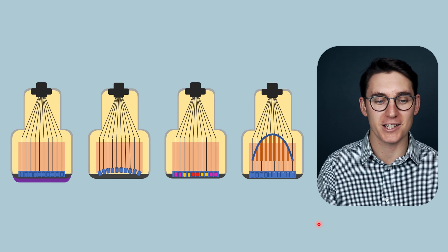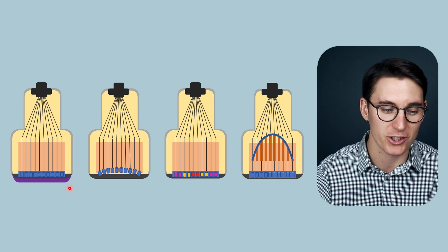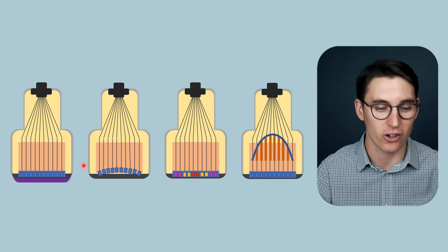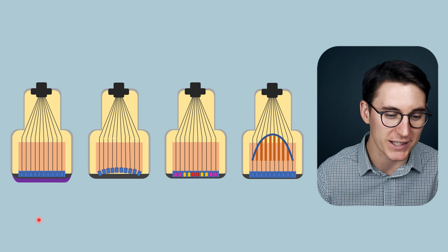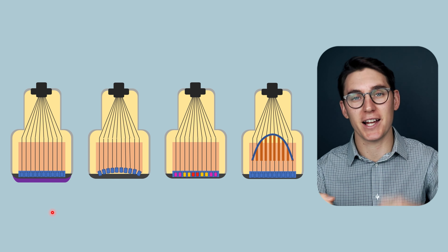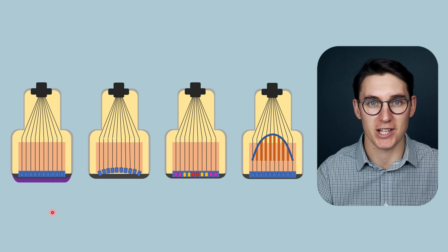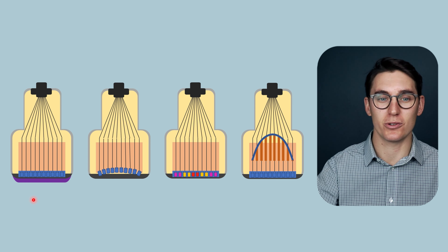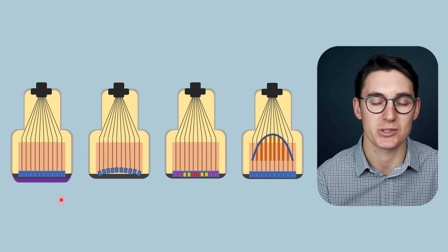There are four mechanisms for changing the focal depth. The first is what's known as an acoustic lens — a material placed on the front side of the transducer that focuses the ultrasound beam to a set focal depth. This is much like a magnifying glass that focuses light at a set focal depth. The acoustic lens has a fixed focal depth; if you want to change it, you would need to swap the acoustic lens.